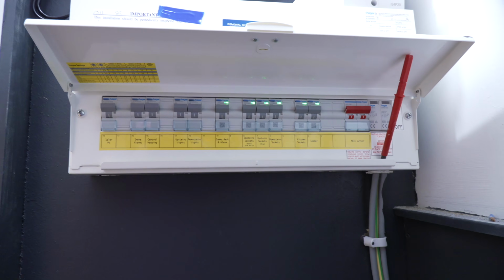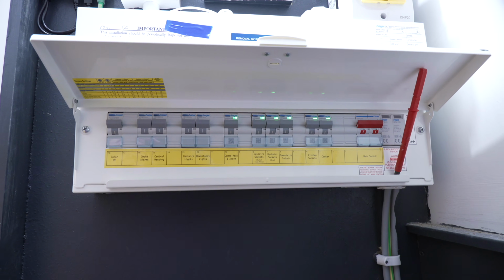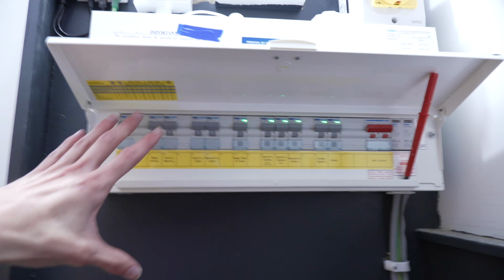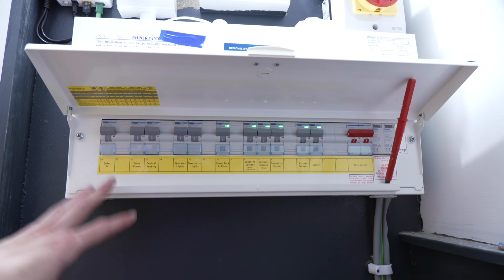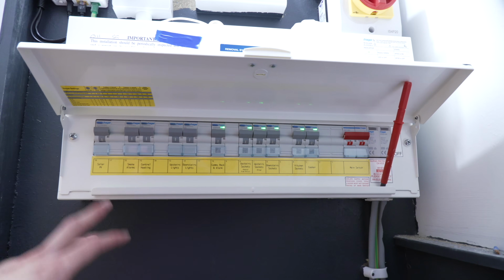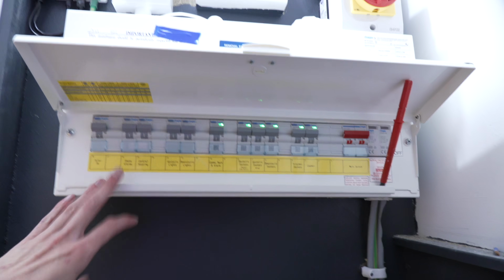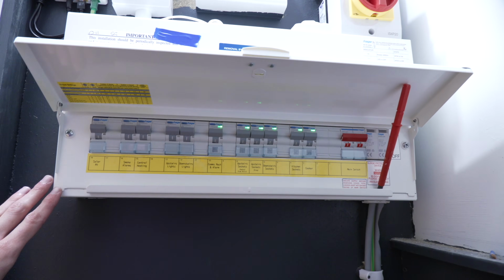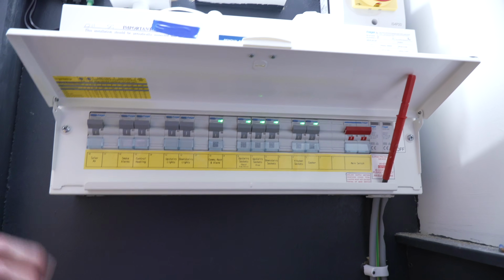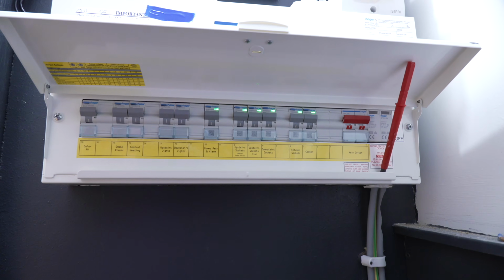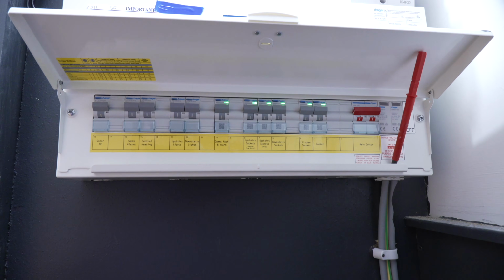So what we now need to do is get all these CTs installed. Of course, the next step involves taking the front off the consumer unit to install the CTs. Now I'm not going to go into too much detail on this, but basically do not do this unless you're competent and you know what you're doing. This isn't the same as just wiring a plug or changing a socket. Make sure you fully know what you're doing, and if in doubt, get a qualified electrician in to do this.